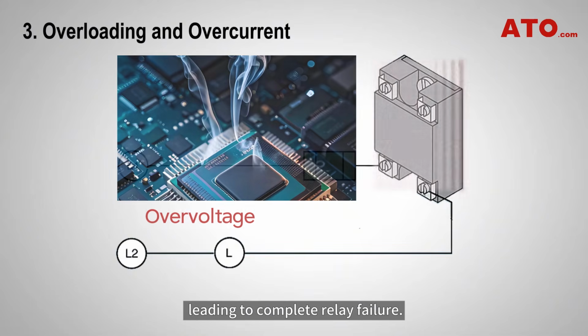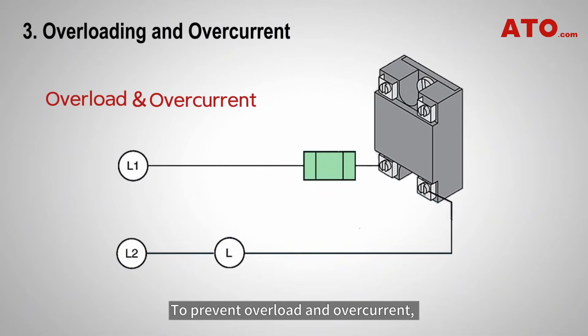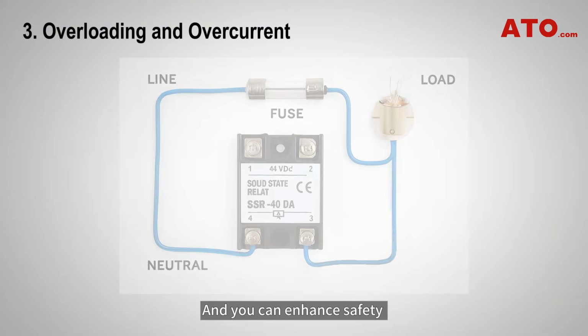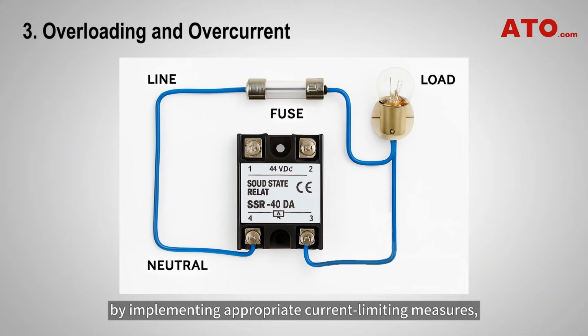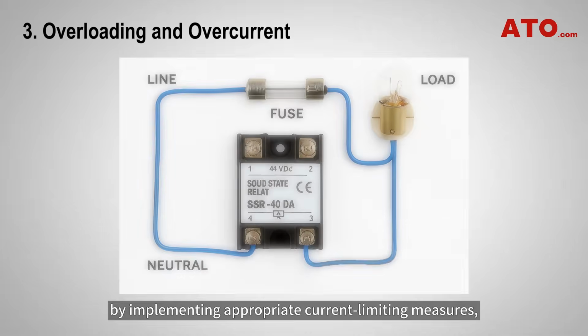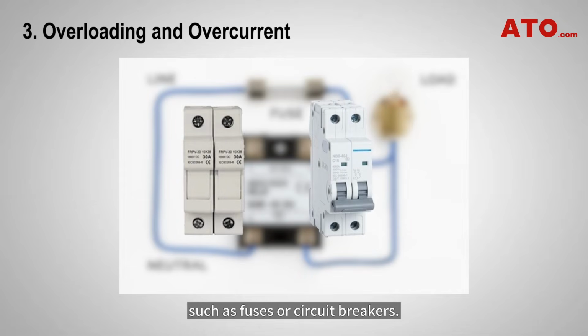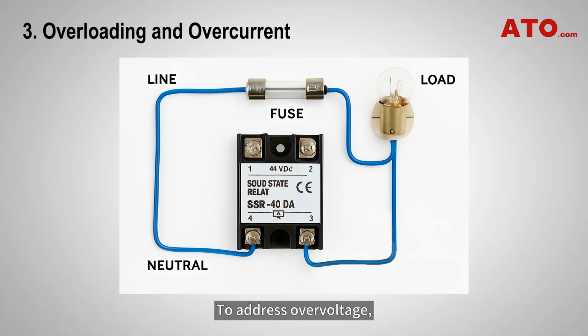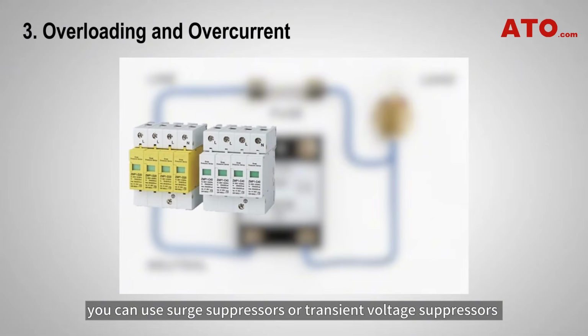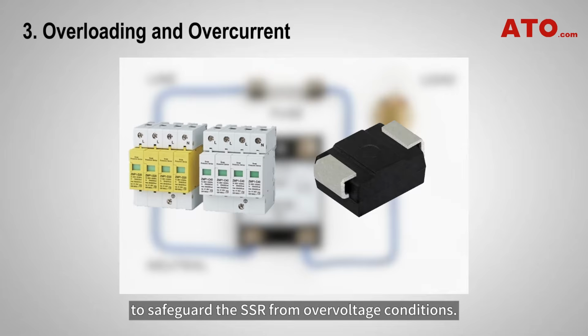complete relay failure. To prevent overload and overcurrent, you need to carefully calculate the load requirements and properly size the SSR for the intended load. And you can enhance safety by implementing appropriate current limiting measures, such as fuses or circuit breakers. To address overvoltage, you can use surge suppressors or transient voltage suppressors to safeguard the SSR from overvoltage conditions.